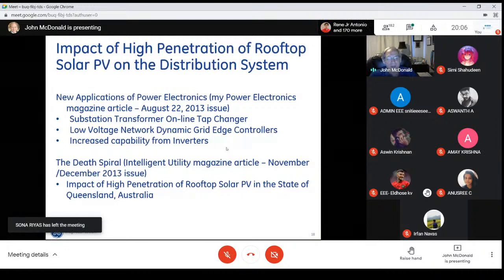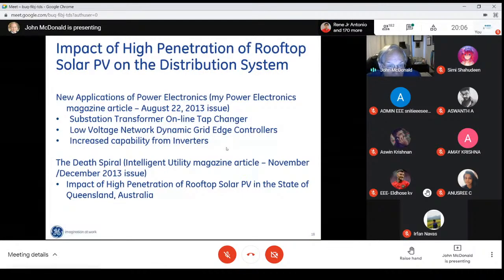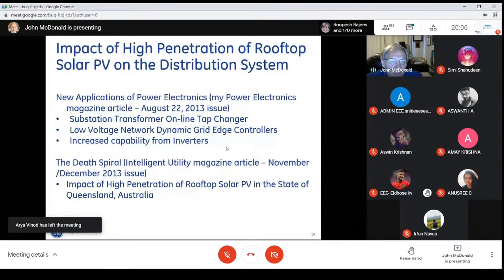This poor tap changer in the substation started operating each day well over 120 times. Its expected lifetime went from 35 years to less than 2 years—it would have to be replaced.